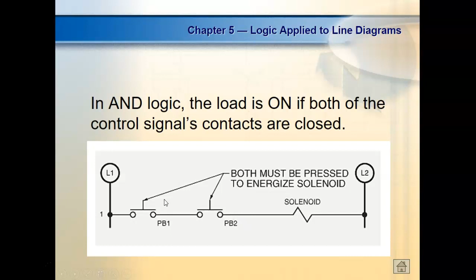Now, why would we want something like that? Well, it could be a safety measure, making sure that both hands are out of something before anything's allowed to start, right? One of the basic ones I can think of is, okay, so here you are, you've made this item, you're about to send it on, but to make sure your hands are clear, or the employee's hands are clear, they have to put both hands on a push button right here to say, hey, my hands are clear. It's known to work. Why? Because it's a very simple and easy way to create a relay control that says, hey, this person's done with their job, their hands are clear, they're not going to get their hands caught anywhere. And if they pull their hands off, the circuit opens and their hands cannot get caught in mechanicals, right? So you can see where something like that could be very important. Doesn't seem like it, but it can be.